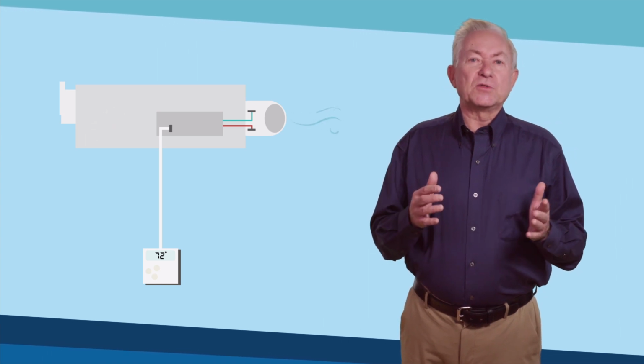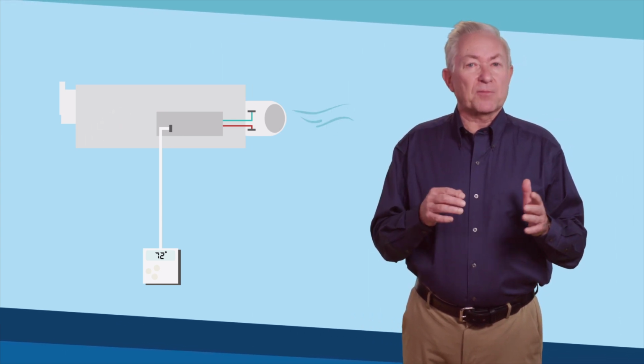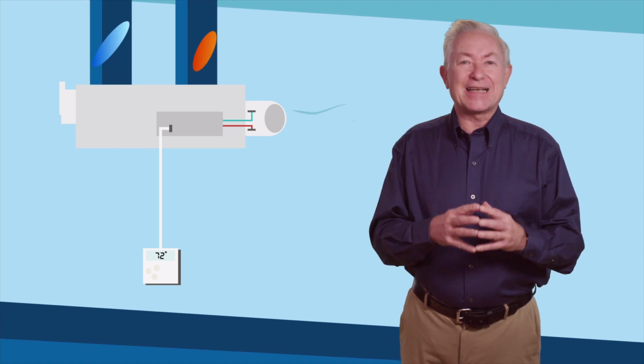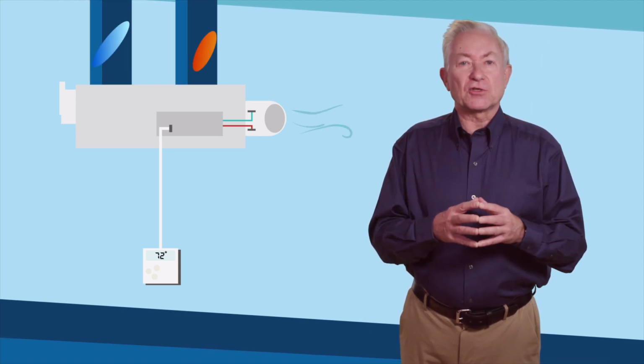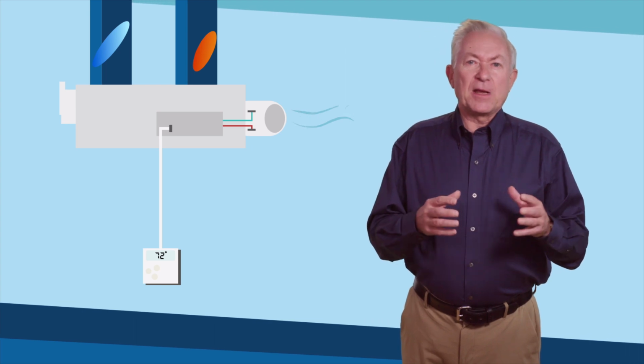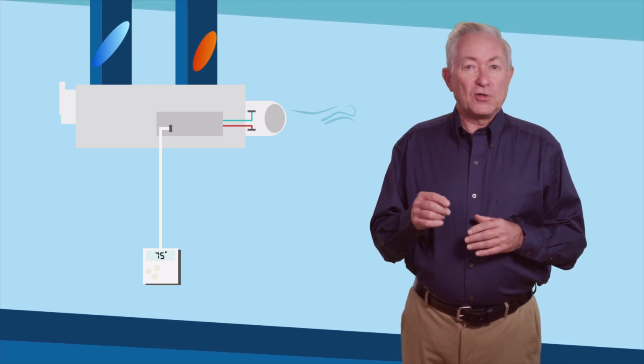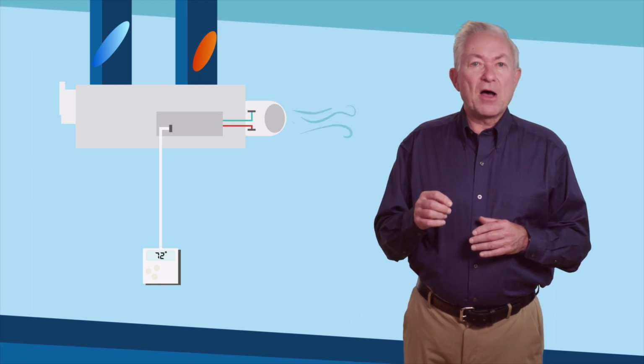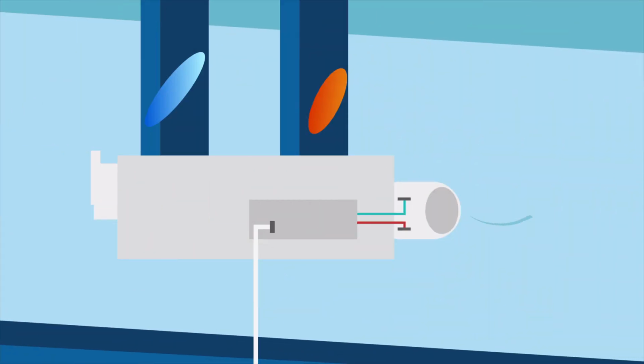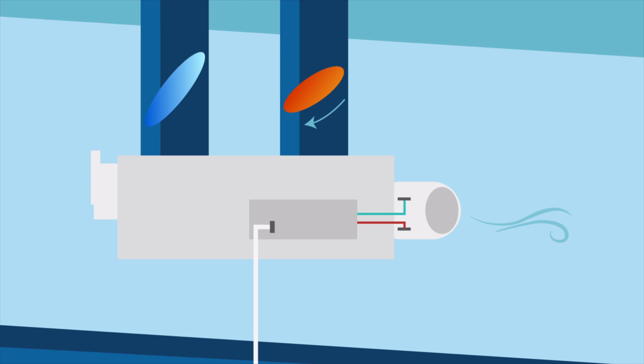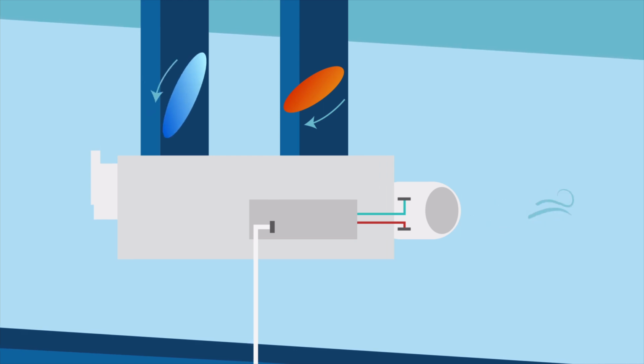For most older systems, the airflow stays constant and the separate hot and cold ducts are mixed inside the box based on the temperature set at the thermostat. This means that if it is 75 degrees in a room and you lower the thermostat to 72, the amount of air will not change. A hot air damper will close and a cool air damper will open to allow all the air to flow through the cool side. A lot of hospitals have a mix of newer and older systems, which can make it more challenging to diagnose issues and maintain proper temperatures throughout the building.